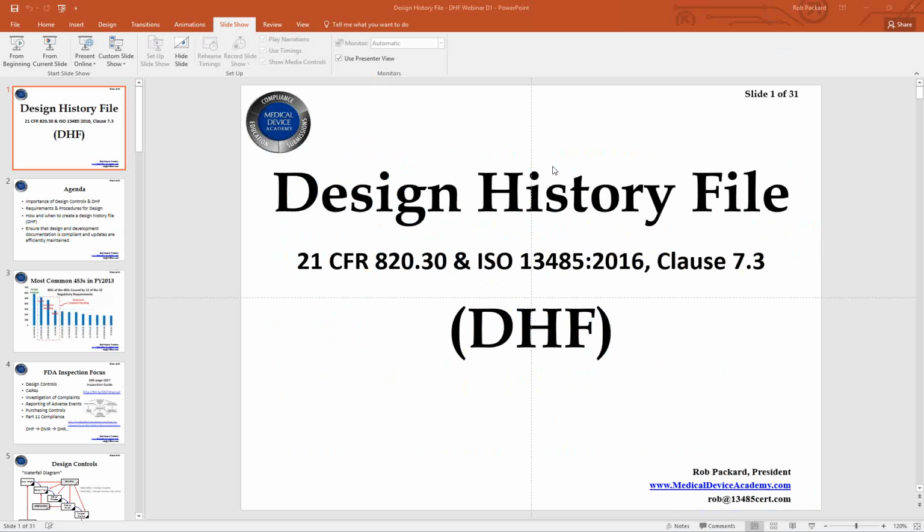And then they say, from my experience, we need to review annually the content of our product DHF and risk management files. If you have a brand new product that you launch on the market that's fairly high risk, you might want to do it at 90 days. If you have a class 3 device, you're going to have to do it at 90 days.